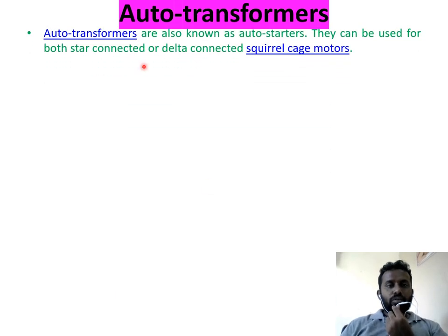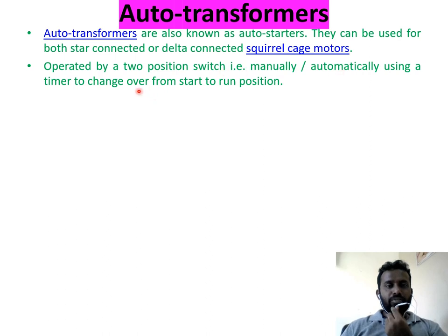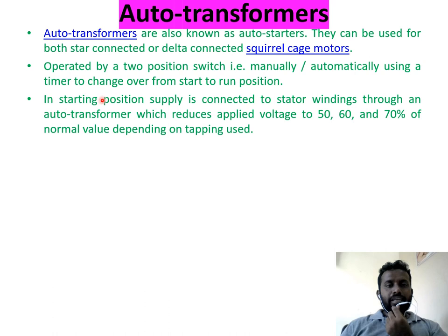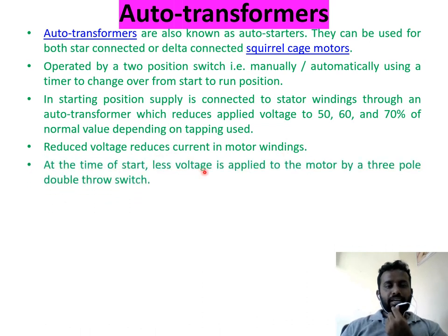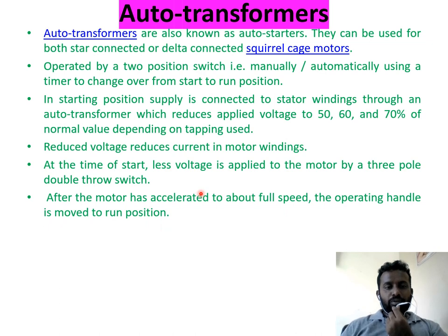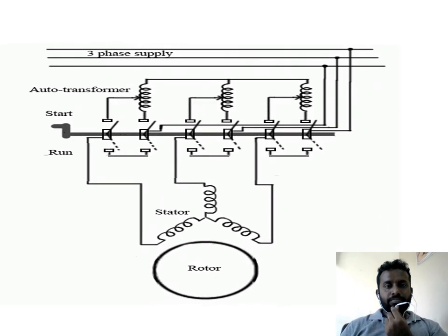Auto Transformer Starting: auto transformers, also known as auto starters, can be used for both star or delta connected squirrel cage motors operated by a two-position switch using a timer to change from start to run position. In starting position, supply is connected to stator windings through an auto transformer, which reduces the applied voltage to 50, 60, or 70 percent of normal value. Reduced voltage reduces current in the motor winding. After the motor has accelerated to full load speed, the operating handle is moved to run position, disconnecting the auto transformer.